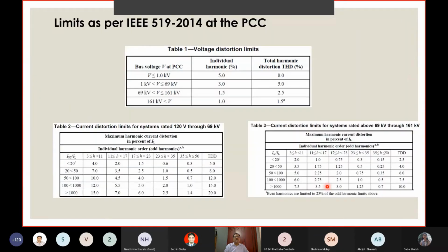So we'll go on. This is the IEEE 519-2014 limits. We have 2 limits or 3 in actual. One is the total harmonic distortion in percentage for various levels of kilovolt ratings. It is presently available in India for 11 kV and above as per the 2019 amendment, and therefore this is what is applicable. 5% THD-V, or THD-U, phase-to-phase voltage. This is the limit. Individual order of harmonic voltage limit is 3%.